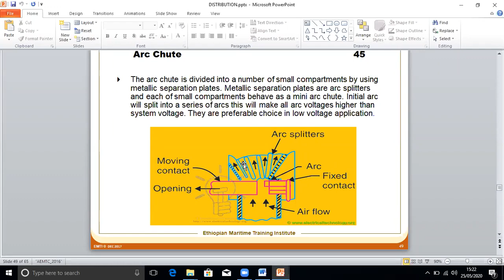The initial arc will be split into a series of arcs. You can see it will be split into a series of arcs. This makes the total arc voltage higher than the system voltage. They are the preferable choice for low voltage applications. So inside an ACB, you have a moving contact, a fixed contact, and an arc chute. This is called the arc chute. These are called arc splitters. The arc between these two is split into small arcs like this, and it extinguishes the arc very fast.